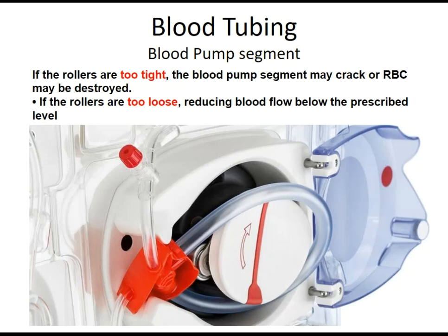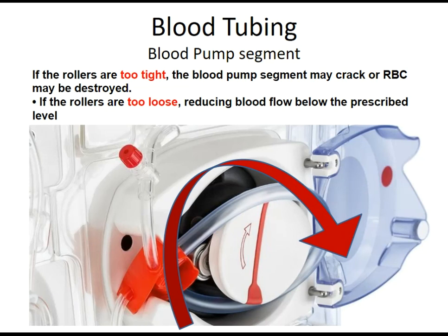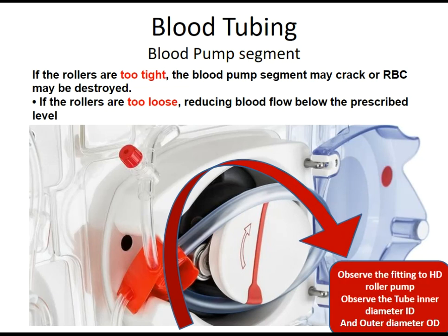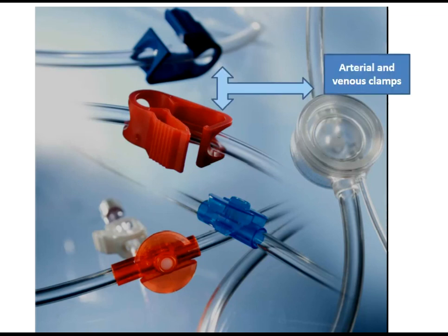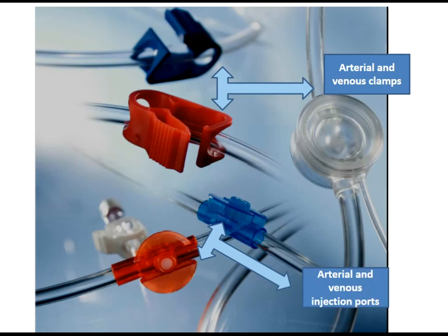If the rollers are too loose, blood flow is reduced below the prescribed level. To avoid fitting issues with the roller pump, observe both the tube inner diameter and tube outer diameter on the blood line itself and on the calibration of the hemodialysis machine. On the blood line, there are also arterial and venous clamps, and arterial and venous injection ports for injection of drugs, anticoagulation, and others.